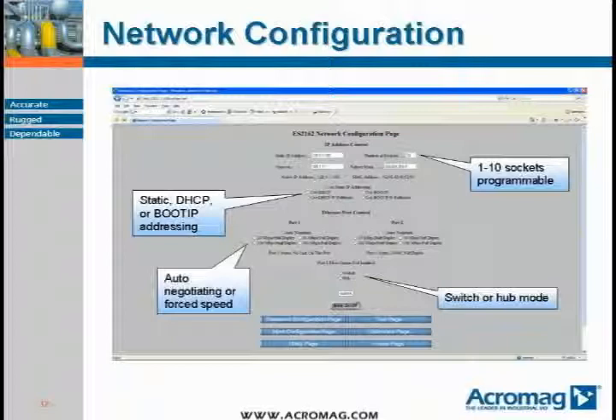Either static or dynamic IP addressing through DHCP or BOOTP may be configured to allow for easy integration into existing network infrastructure. Auto-negotiating is also configurable per port, or speed can be forced. Finally, on the network configuration page, the ES2161 and 62 module may be configured as a hub to allow integration into applications utilizing redundancy for high reliability.